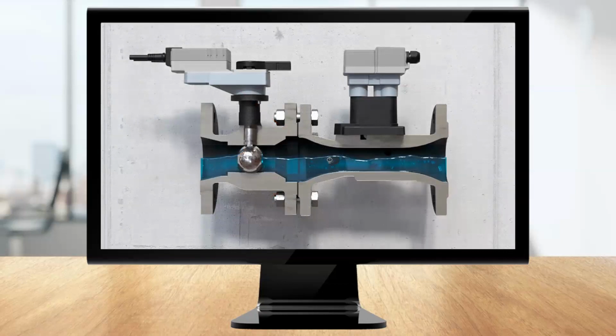The second way is an energy valve, or an EPIV, an electronic pressure-independent valve. It's actually a simple product to understand. It has the same design as an airside VAV. Both use a flow-measuring device: an air sensor on a VAV, and an electronic flow sensor on an EPIV. This one is an ultrasonic flow meter with temperature and glycol compensation. It's chosen for its lack of moving parts and its low drift and maintenance requirements. Each one has a controller that accepts the flow measurement and logic that modulates the regulating device. The valve actuator plays this role for an EPIV and interprets the control command as a specific GPM. The regulating device is represented by a damper on the VAV or a valve on the EPIV. The valve is driven by the actuator to achieve the proper flow rate.